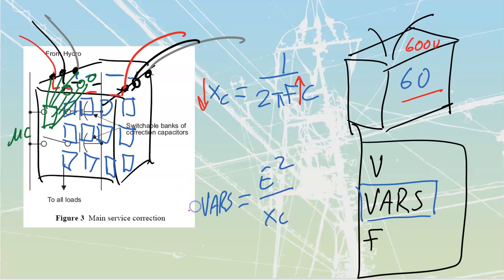What we are going to see, though, is a reduction in the total amount of VARs. That rating this thing had in VARs before is going to drop, because I'm dropping my value of E squared, which means I'm dropping my value of VARs out of this thing. Once again, you'd just have to go through a set of calculations. You can use them on a lower voltage, but you'll get less VARs out of it — it's not a direct relationship, it's a squared type of relationship.